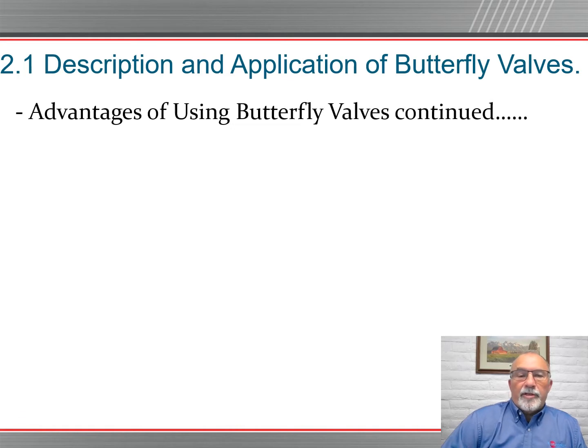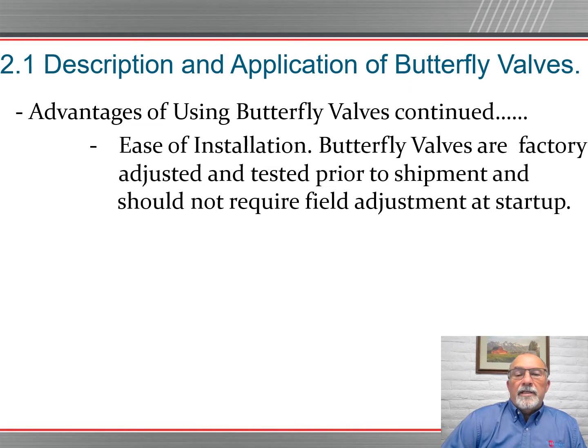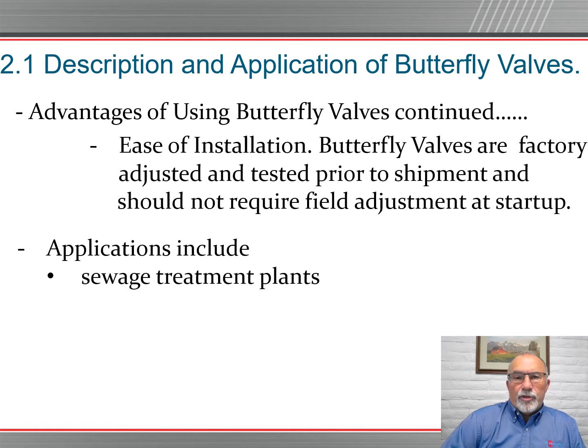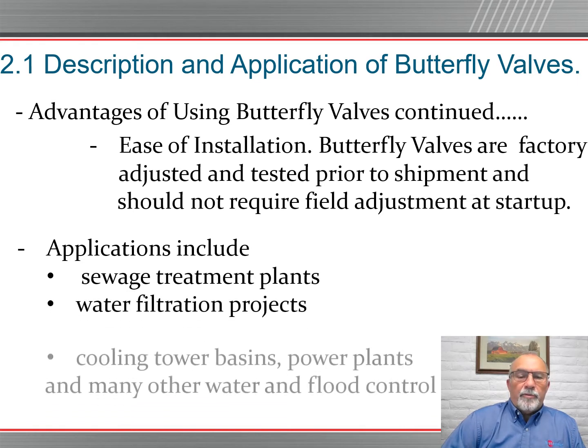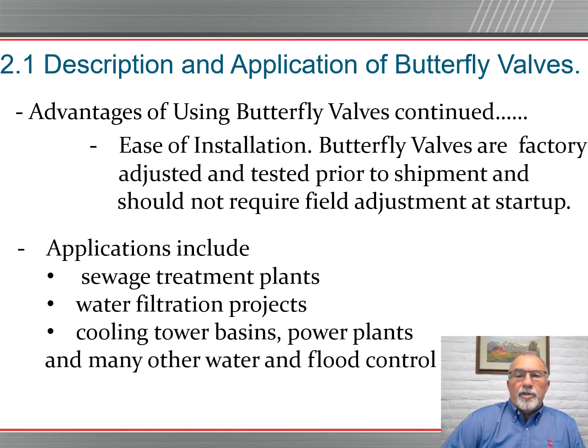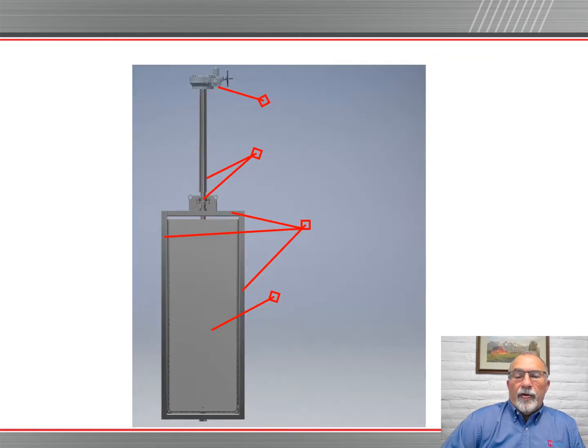More description of application of butterfly valves. Advantages of using butterfly valves: ease of installation. Butterfly valves are factory adjusted and tested prior to shipment and should not require any field adjustment at startup. They're shipped as one unit, one single piece that can just be installed as one unit. Applications can include sewage treatment plants, water filtration projects, cooling tower basins, power plants, and many other water and flood control projects. Here's a diagram of a typical Waterman butterfly valve.